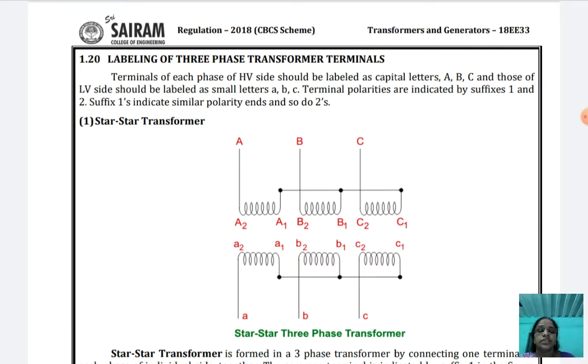In this case, you remember that the capital letters should be labeled, that is, indicated for the HV side only. And the terminal of each phase of the LV side should be labeled with small letters a, b, c. So you can keep it in your mind: capital letter means HV side, small letter means LV side only.